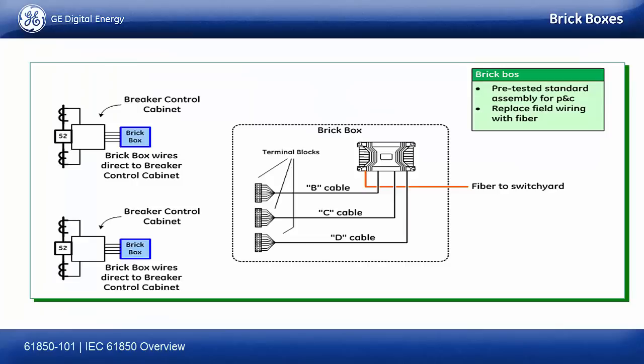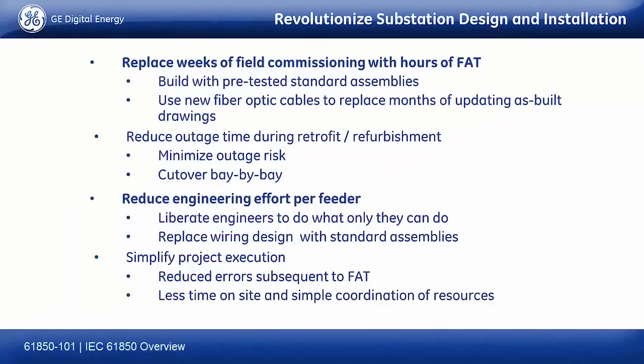I can test my whole protection and control system in my manufacturing environment before I send it to the site, so it's ready to connect, right? I can reduce the outage time during refurbishment. I can reduce the engineering effort per feeder, right? This is one of the great things about process bus. We can stop doing wiring.